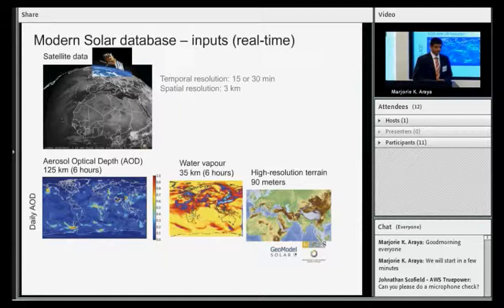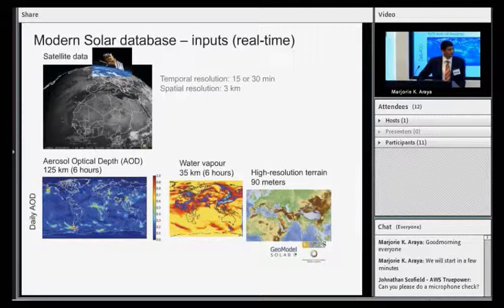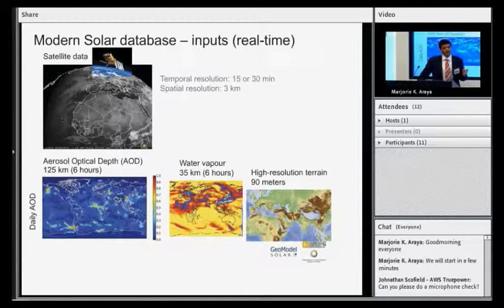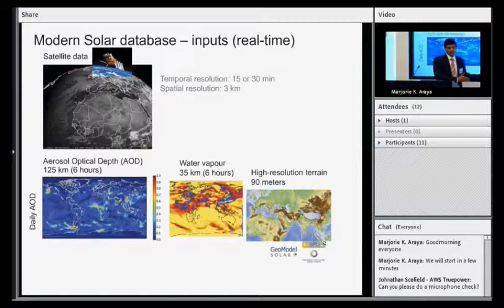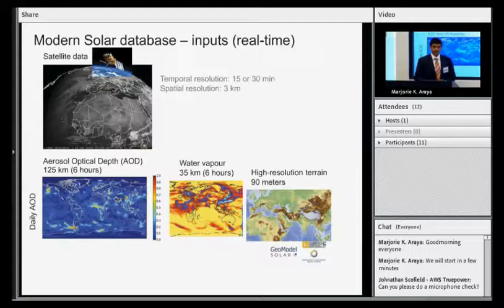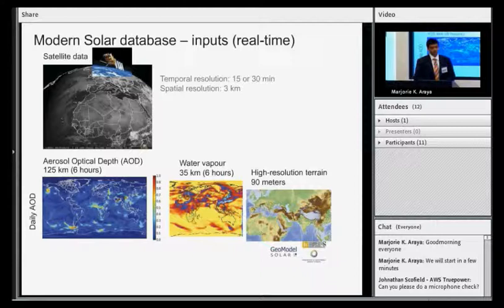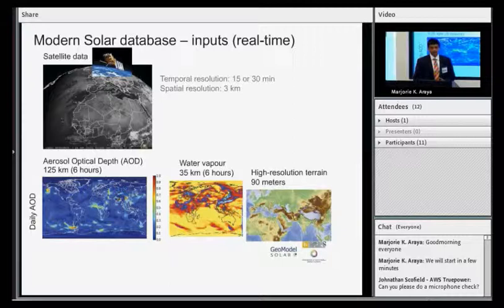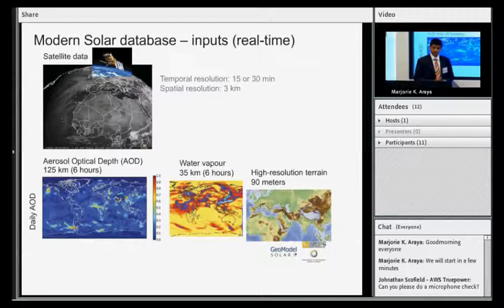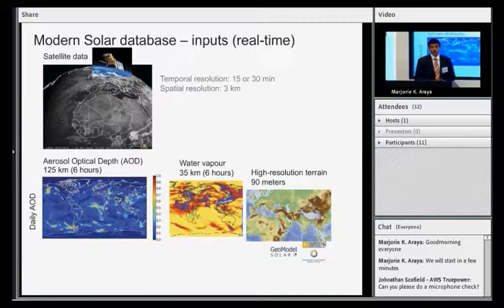The good news is that with modern modeling technologies and data inputs, it's already possible today to map at a very high resolution the solar resource across the world. What constitutes a modern satellite-based database? The inputs that we should be looking at is high-resolution spatial data at something around 3 to 4 kilometers at least, data that is updated live and not based on static data which was measured 5 or 10 years ago. And something we've spoken a lot about today in the earlier session is information on aerosol optical depth, or in simple words, the amount of pollution or dust that is there in the atmosphere.